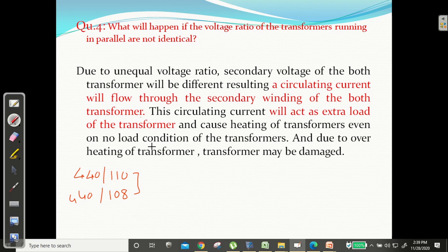This circulating current will act as extra load on the transformer and cause heating of the transformer even in no load condition. And due to overheating the transformer may be damaged. It depends on the loading. If there is 100% loading or a difference, circulating current will be there, and because of the circulating current more and more current will flow. Okay, so it may damage the transformer. So the ratio should be same.